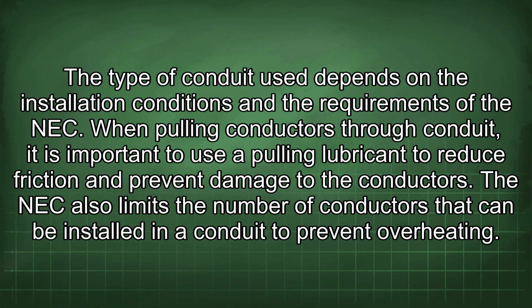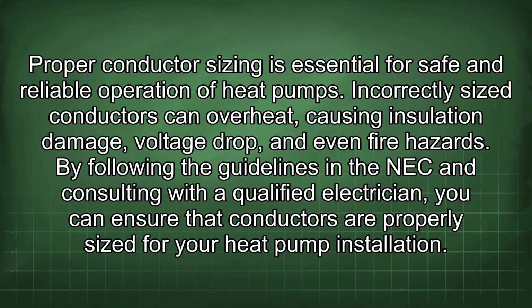When pulling conductors through conduit, it is important to use a pulling lubricant to reduce friction and prevent damage to the conductors. The NEC also limits the number of conductors that can be installed in a conduit to prevent overheating. Proper conductor sizing is essential for safe and reliable operation of heat pumps. Incorrectly sized conductors can overheat, causing insulation damage, voltage drop, and even fire hazards. By following the guidelines in the NEC and consulting with a qualified electrician, you can ensure that conductors are properly sized for your heat pump installation.